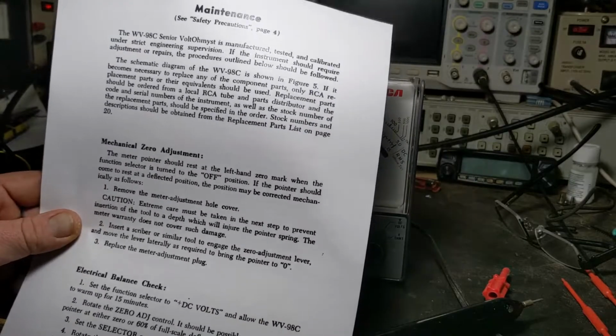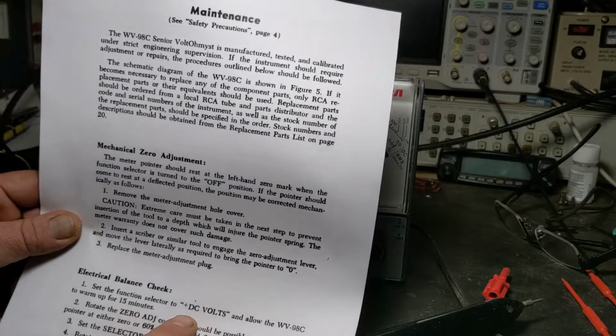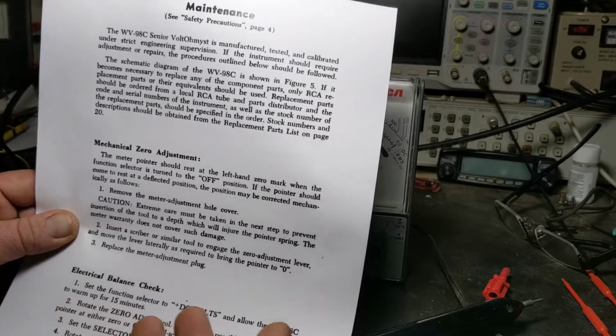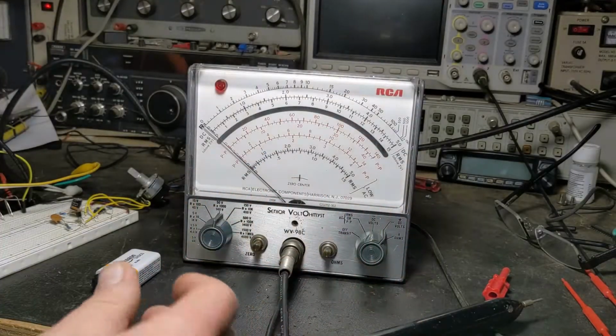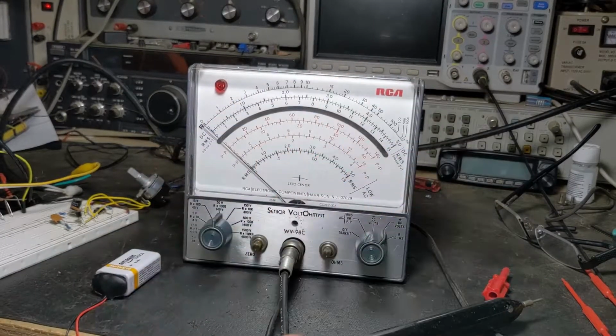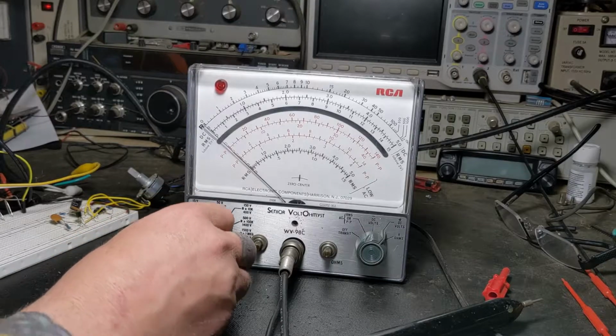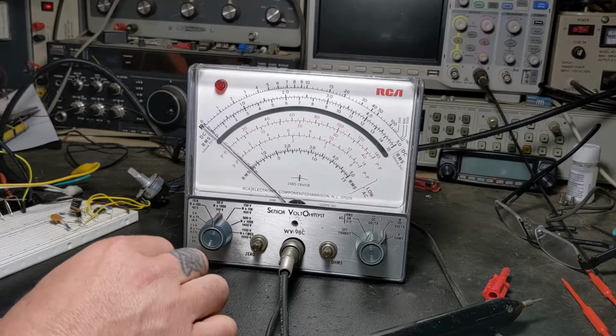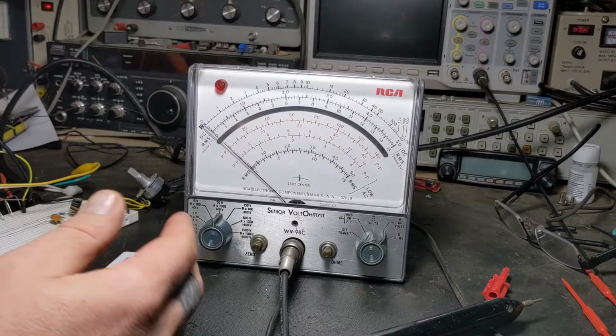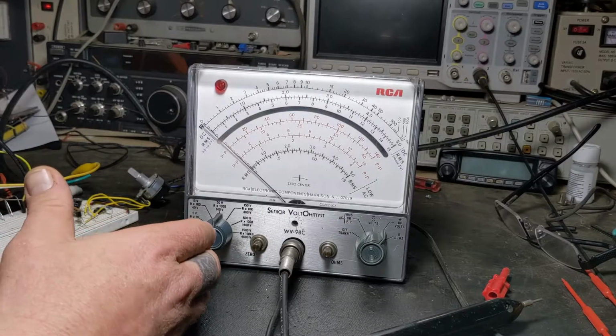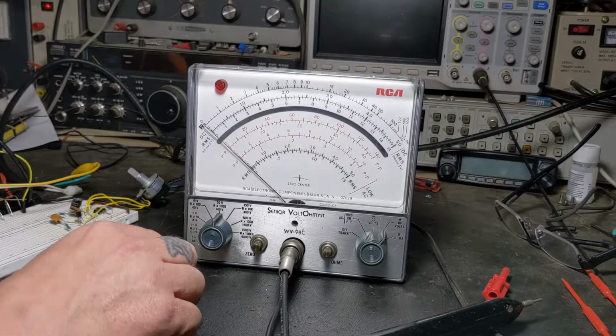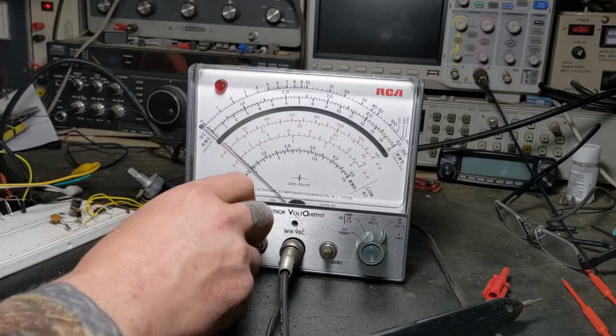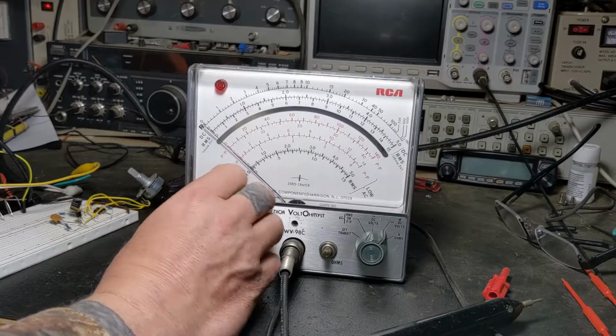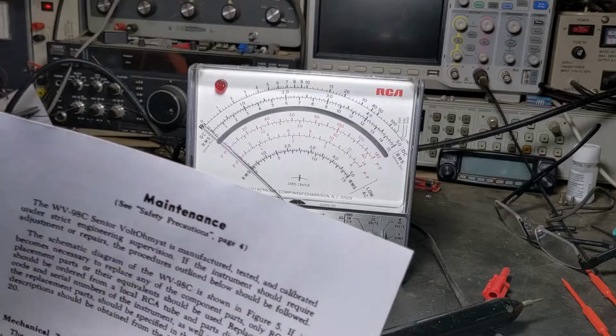And then electrical balance check, set the function selector to DC volts, and allow it to warm up for about 15 minutes, which this has been warming up for a while, but we'll put it over on 15 volts. I had it on 50 volts, messing with this battery here. I checked this battery on the other meter over here, and it's a little bit less than 9 volts, like 8.8. And this here's reading right below that, so it's not bad. But anyway, go to 15, select 15 volts there.